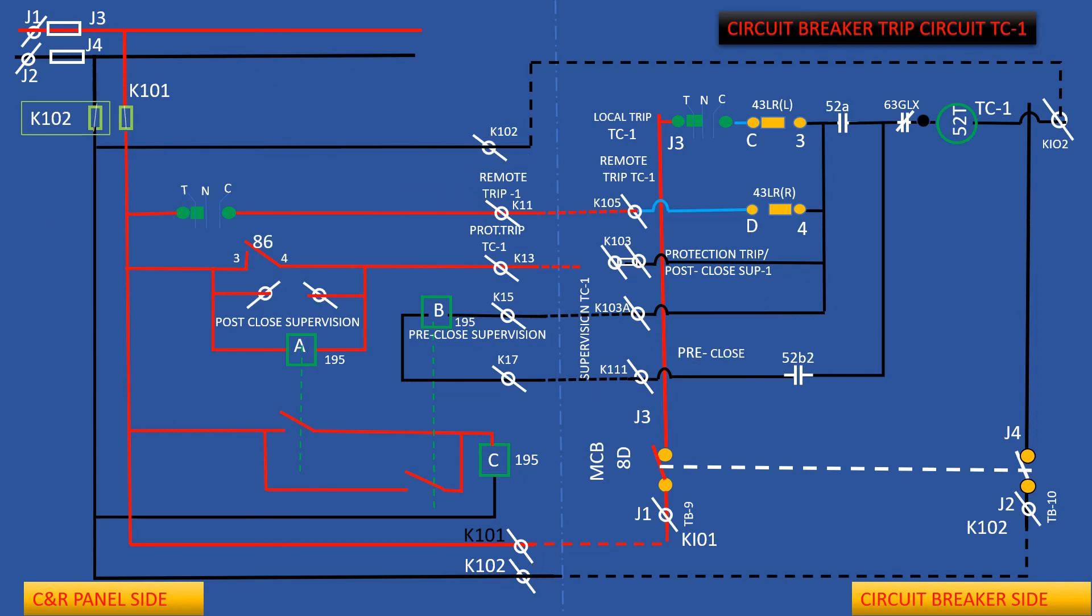The same procedure has to be followed either at pre-close or at post-close trip circuit. Only difference is contact conditions at 52a and 52b auxiliary contacts. Before closing the circuit breaker, 52b will be closed and 52a will be opened. After closing the circuit breaker, it will be reversed - 52b will be opened and 52a will be closed.